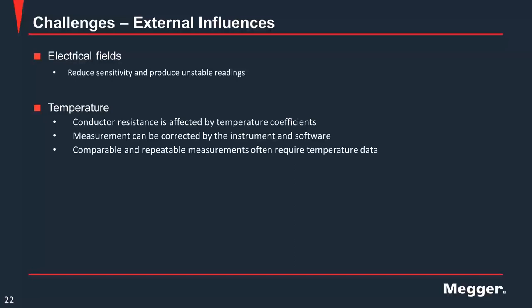So this is very important, you take note of the temperature when you do testing, because it can be corrected by the software to get the result so it can be comparable. Otherwise, you cannot compare the previous measurement with the present measurement, because maybe the result is quite a big difference with different temperature when you did the testing. This is also the challenge, electrical field and the temperature.